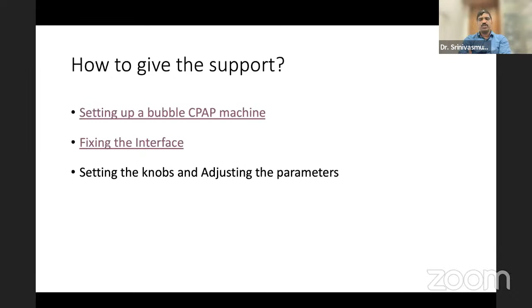Immediately you need to see if the flow rate of 5 liters per minute is adequate or not by looking at the bubbles in the bubble chamber. If bubbles are there in the bubble chamber, your flow rate is adequate. If there are no bubbles, you need to increase the flow rate or look for leaks in the circuit. Next, see whether the retractions are coming down. The moment you connect the baby to CPAP, the grunt will disappear, nasal flaring will come down, and the retractions will start showing improvement. This shows that the pressure is going to the lungs and recruiting the alveoli. The alveoli are opening up and the FRC is improving.